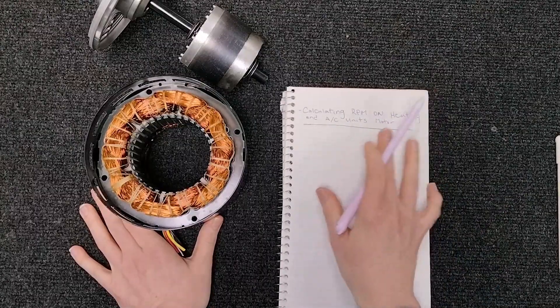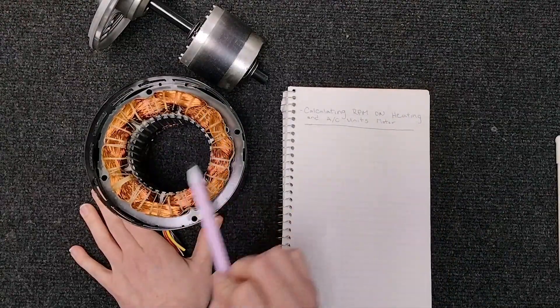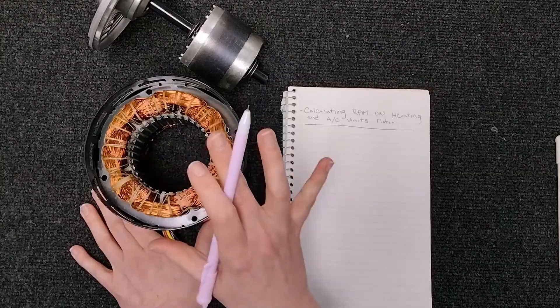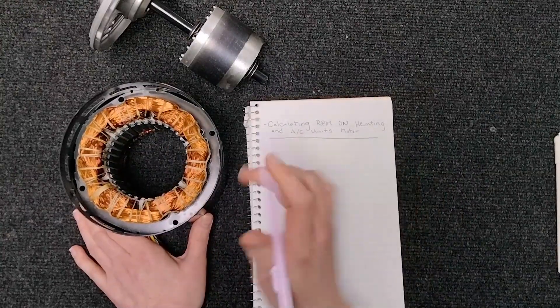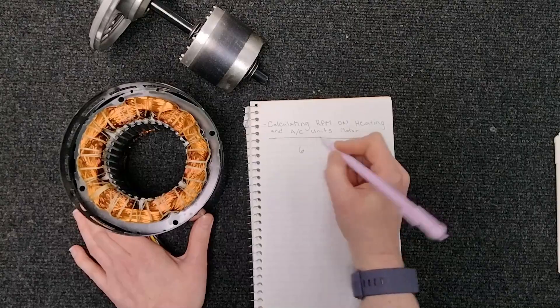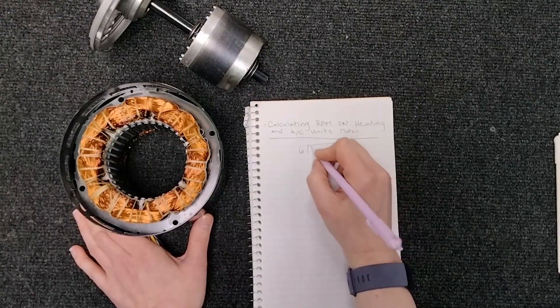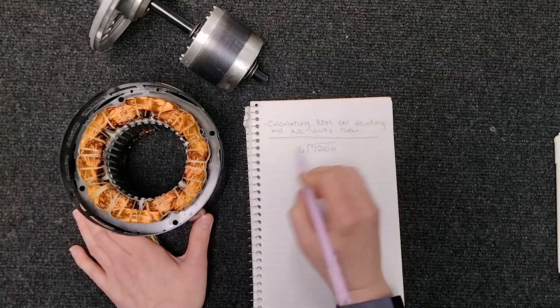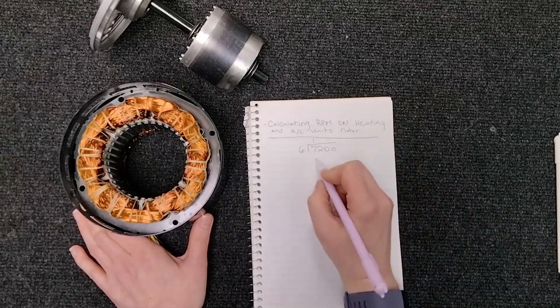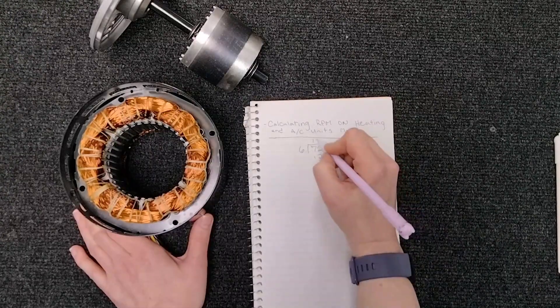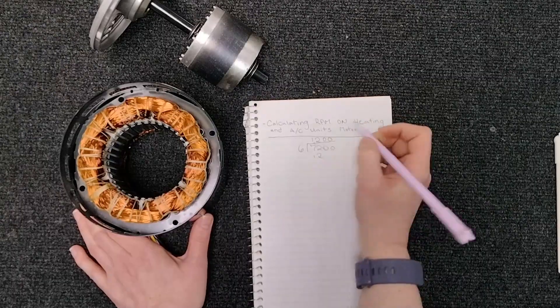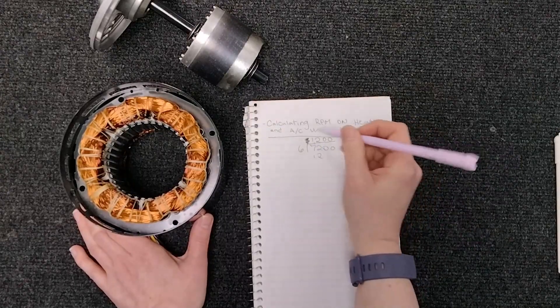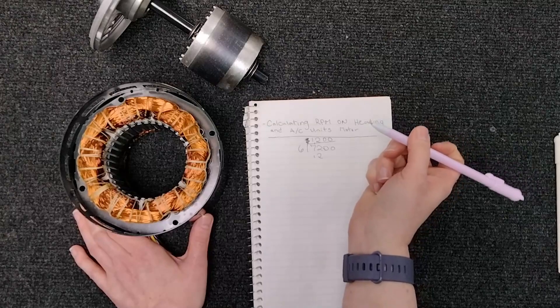So when we're calculating this, we're going to take these poles. This is on an AC voltage motor. DC is going to be different. So on an AC motor we're going to divide 7200 by the number of poles. And so obviously we're going to do our math here and add our zeros. And now we know it's 1200 RPM.